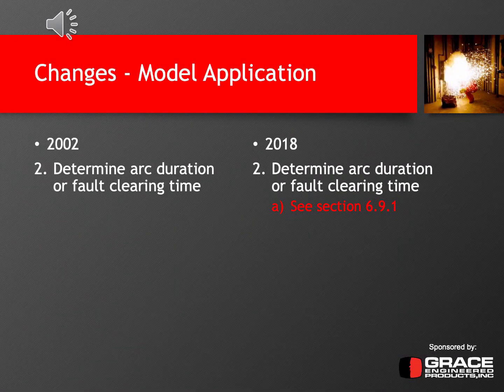So once the arcing current has been determined, the next step is to determine the arc duration or the fault clearing time. And this is basically a review of the protection settings and maybe reviewing some TCCs, or time current curves, to determine how long it'll take at the calculated arcing current to clear the arcing current. These steps are very similar, and in 2018 there's an additional section that says see section 6.9.1 for further guidance.